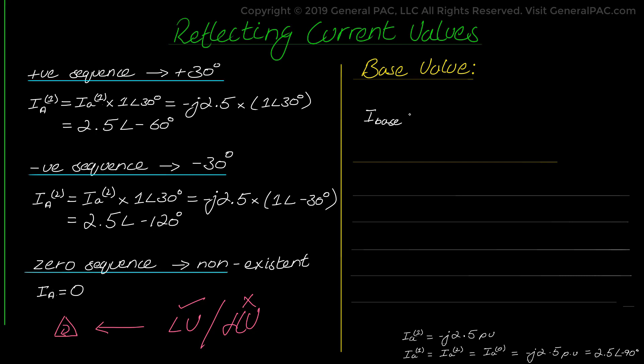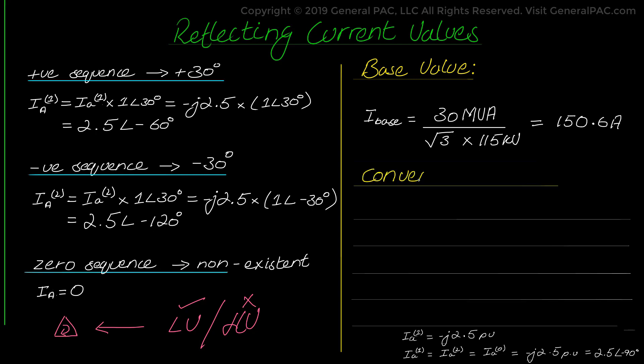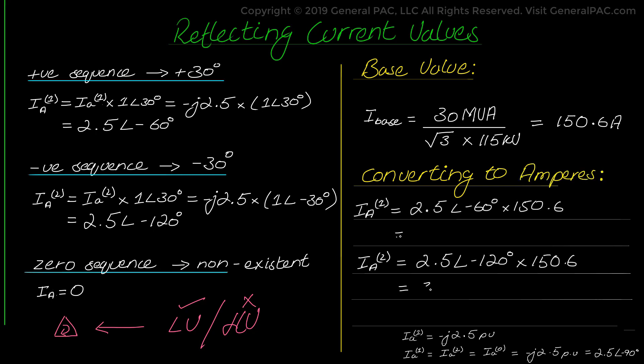Since we are working on the high-voltage side of the transformer, we divide the base value of power, which is 30 MVA, by the high side voltage of 115 kV, to get a base value of 150.6 amps. Then we multiply the per unit values with the base values to get ampere quantities. We get 377 amps at angle negative 60 degrees as the positive sequence current and 377 amps at angle negative 120 degrees as the negative sequence current.